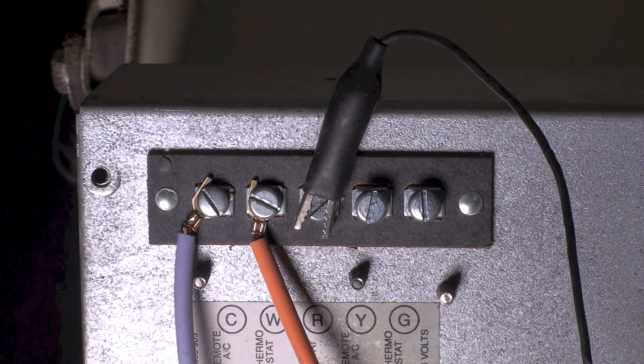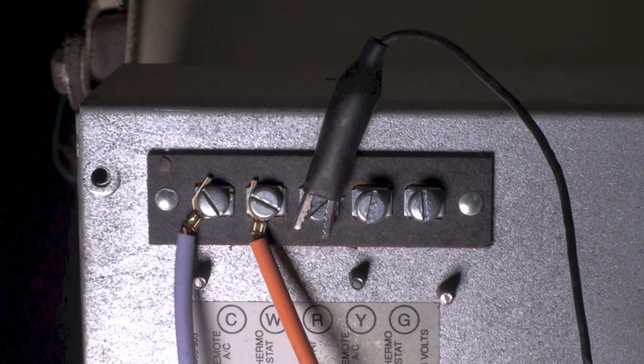You know that if it works when you jumper it and doesn't work when it's not jumpered, then the thermostat or the wiring to the thermostat has to be the problem.